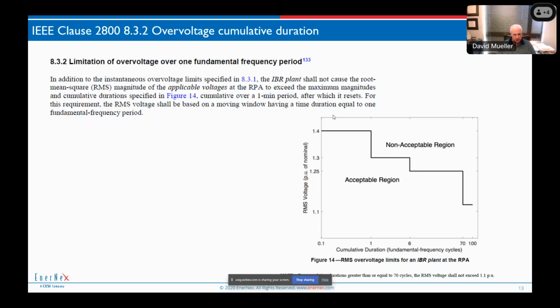Cumulative overvoltage is another trap. Here we're talking RMS, not instantaneous. We're not talking about things on top of the wave shape. We're talking about RMS values, primarily. Although, interestingly enough, the graph shows subcycle cumulative duration. It says we should calculate RMS over a cycle, but then it gives a limit for subcycle. So I'm not sure how to apply that, but I know that for the multiple-cycle events, it's pretty clear. We're going to do one-cycle windowing. We're going to calculate the cumulative amount of time over a one-minute period that we're above a certain voltage level, and we have to stay below that.